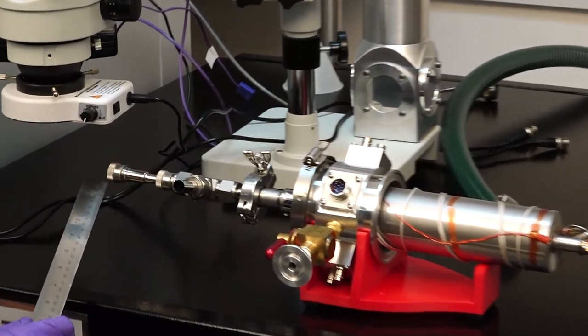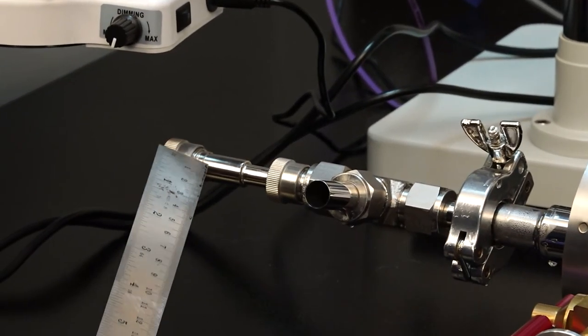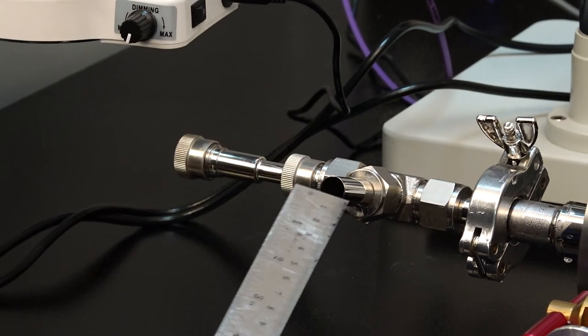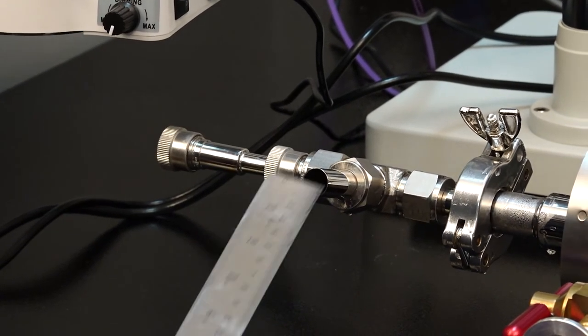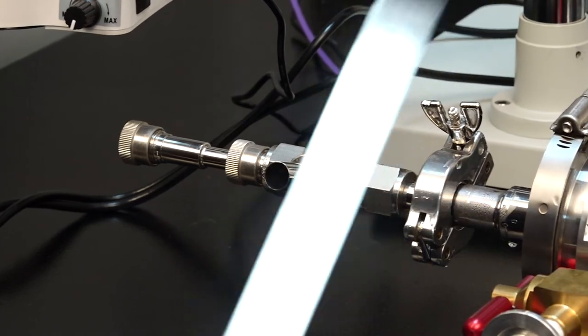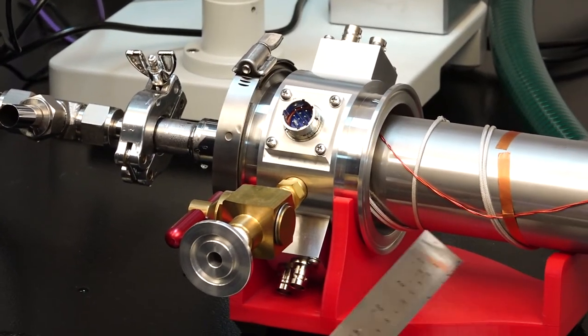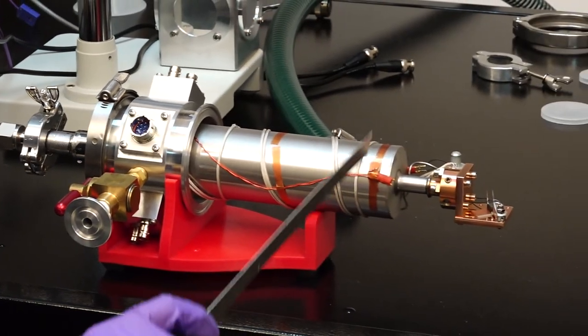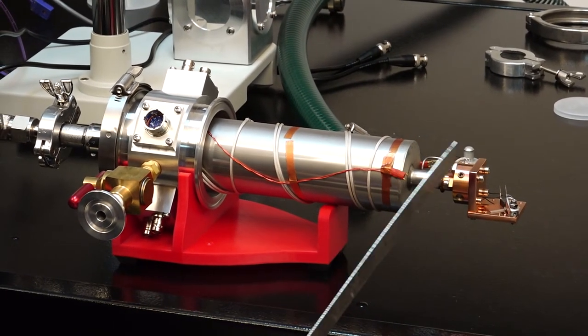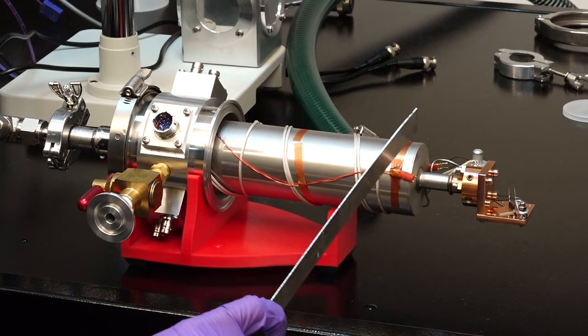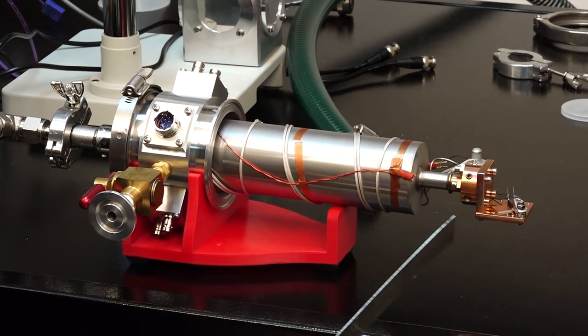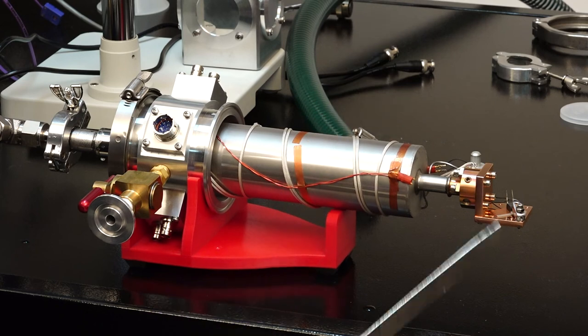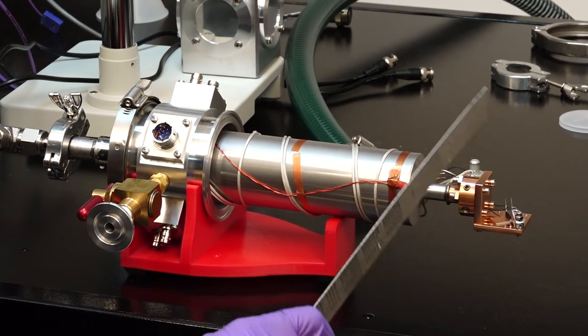First, to the left is from where we will be pouring the liquid nitrogen. This is the indicator for whether the nitrogen has filled up the column. Secondly, is this chamber which holds the liquid nitrogen and which cools the sample through a cold head connection here. The temperature is conveyed to the sample stage. So this L-shaped stage is a sample stage wherein we would be loading our samples.